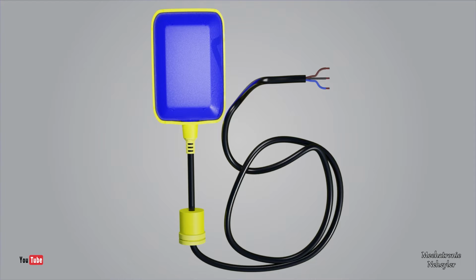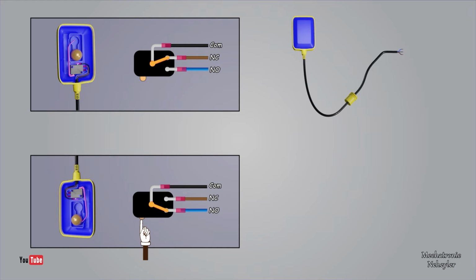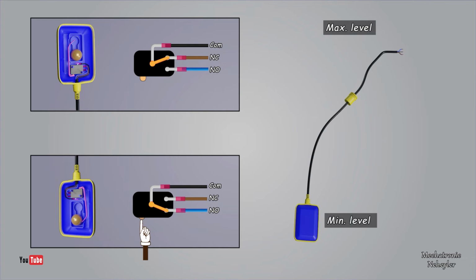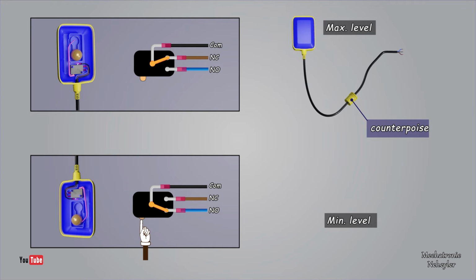The electric float consists of 3 cables. A common cable, which is usually black. A brown normally closed configuration cable, and a light blue normally open configuration cable. This device can be found in 2 possible situations: at a maximum level and at a minimum level. The distance between these 2 points will depend on how short or long the cable is from the counterweight to the head of the float, since it moves with respect to the counterweight.